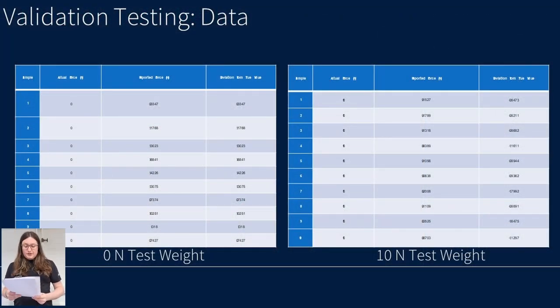Validation tests were performed to ensure the system was returning values within expected ranges. Given the nature of strain gauges, results within a 10% variance from the true value were expected. These tables show the results of the initial validation test. Many of these values fall outside this expected 10% variance; however, the results prove the system was returning useful data.